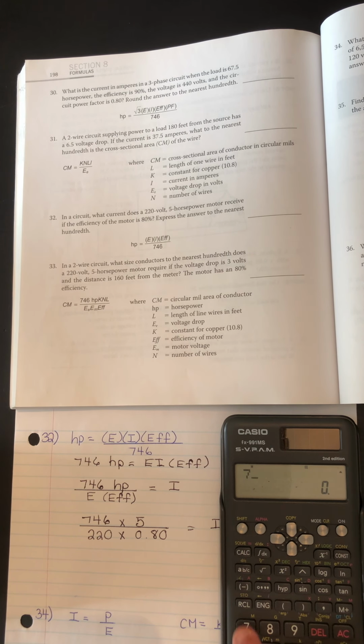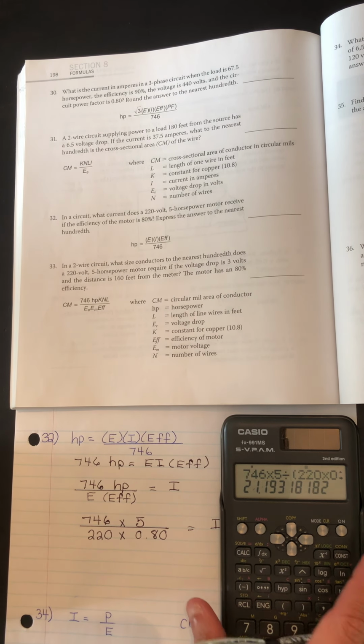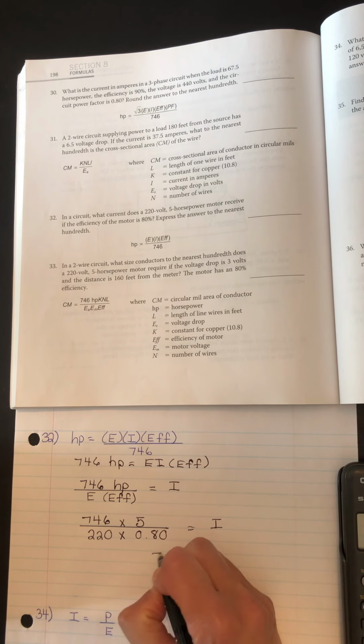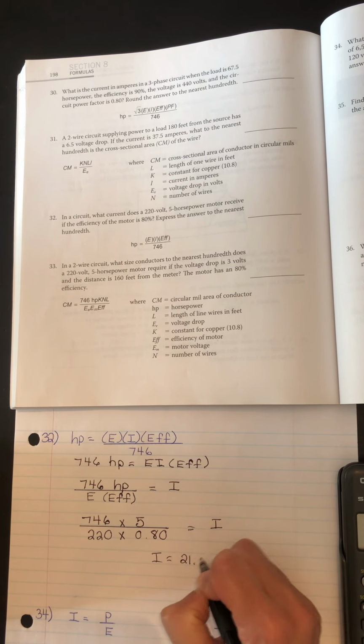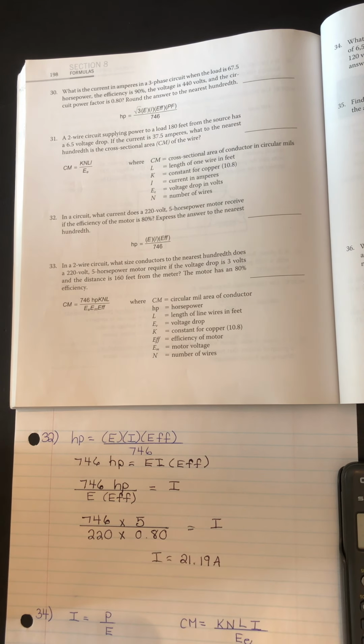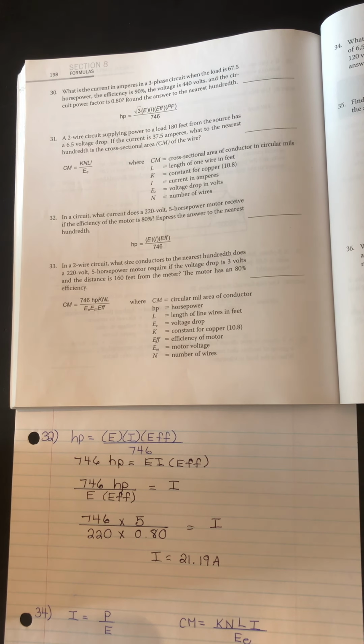Or 746 times 5 divided by, in a bracket, 220 times 0.80. So either way, of course, we'll get the same result. This will be 21.19 amps. Okay, so that's problem 32.